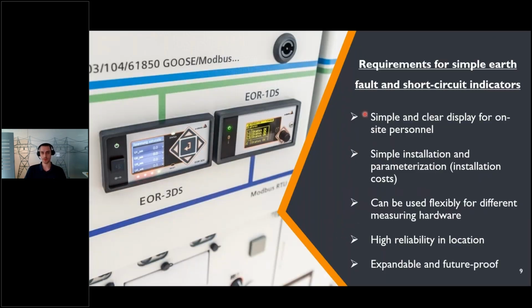The requirements for simple earth fault and short circuit indicators are that they should have a simple and clear display for on-site personnel. They should be installed simply, and also the parameterization should be simple in order to reduce installation costs. They should be able to be used flexibly for different measuring hardware, and of course have high reliability in fault localization. That is still the main focus of our devices, of course. And also these devices should be expandable and future-proof.